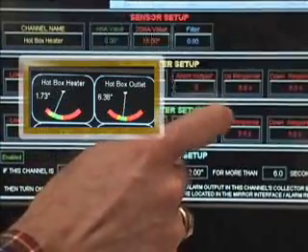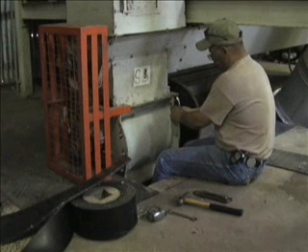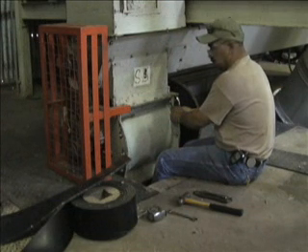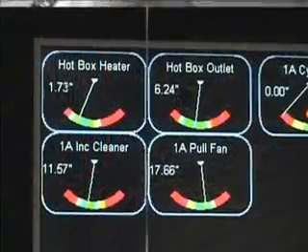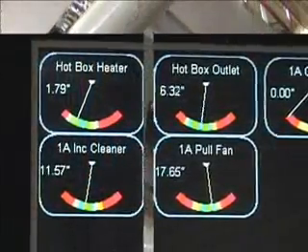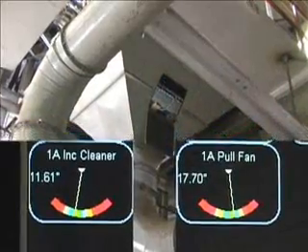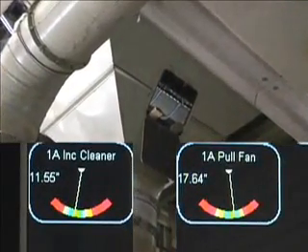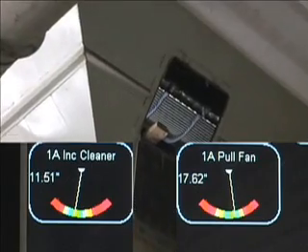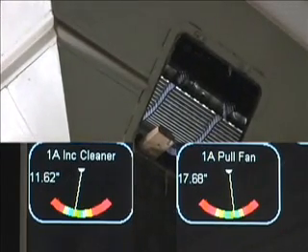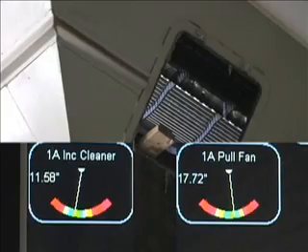Moving further along in our example gin, the principles just applied to the hot box may also be applied to any blow box with a vacuum dropper. Setting alarm conditions for a pressure drop at a location like this can give you an excellent indication of when the flights of the vacuum need attention. It can also be a helpful tool when adjusting the feed rate with wet cotton that tends to resist flow and choke.